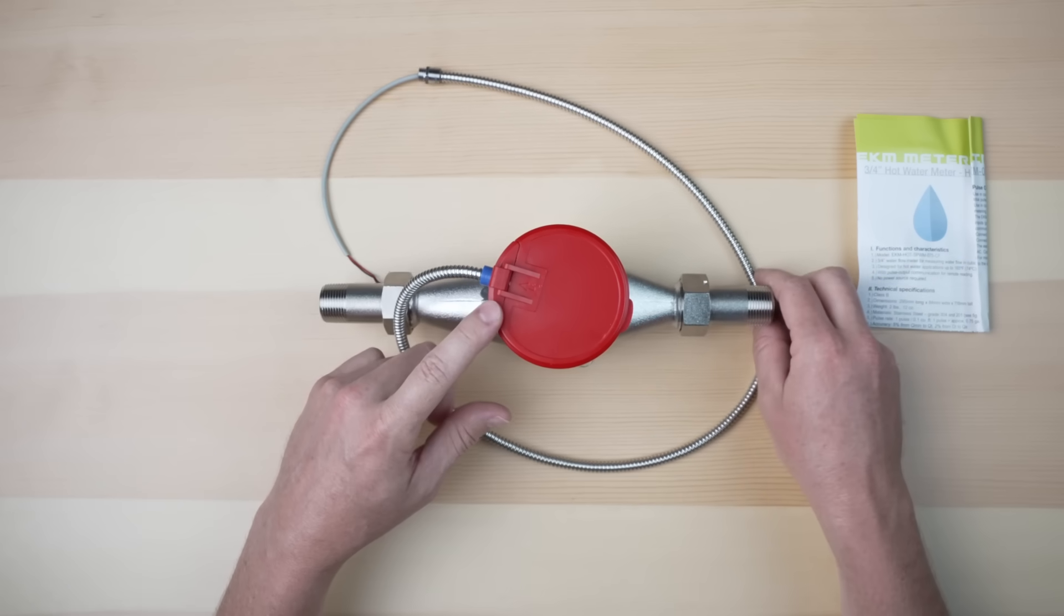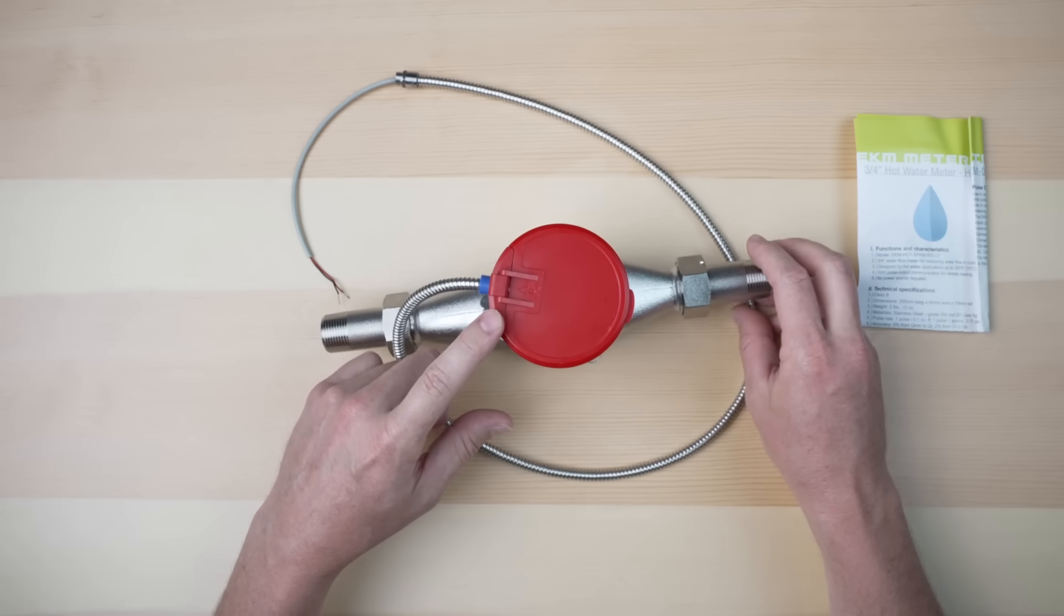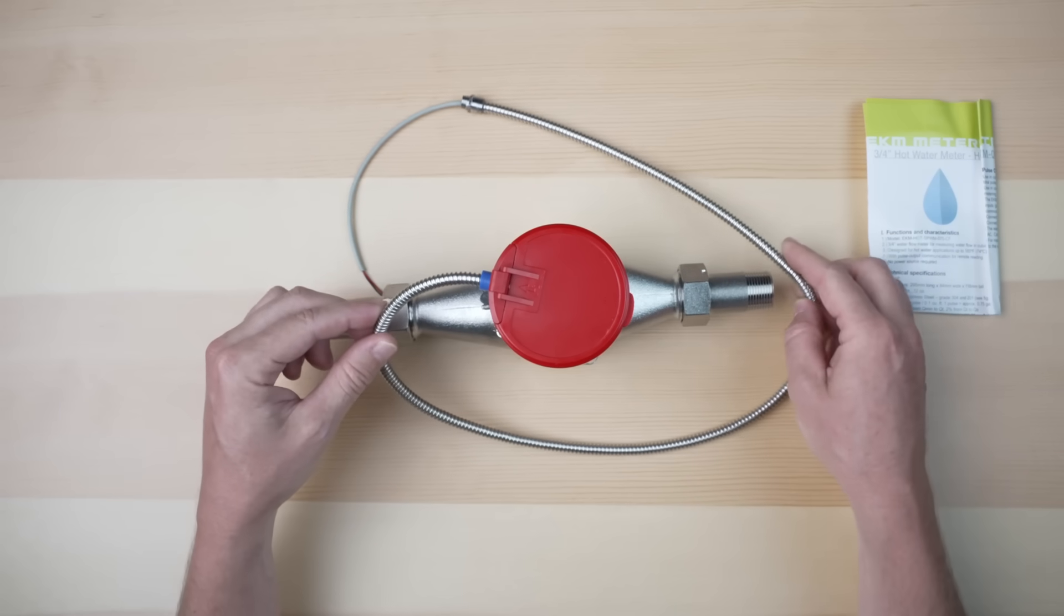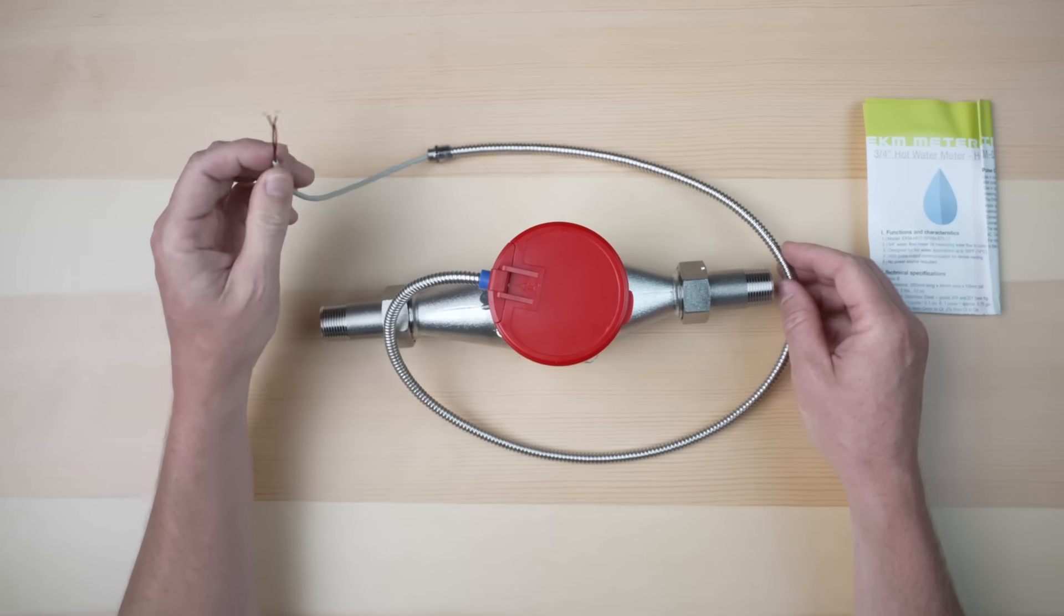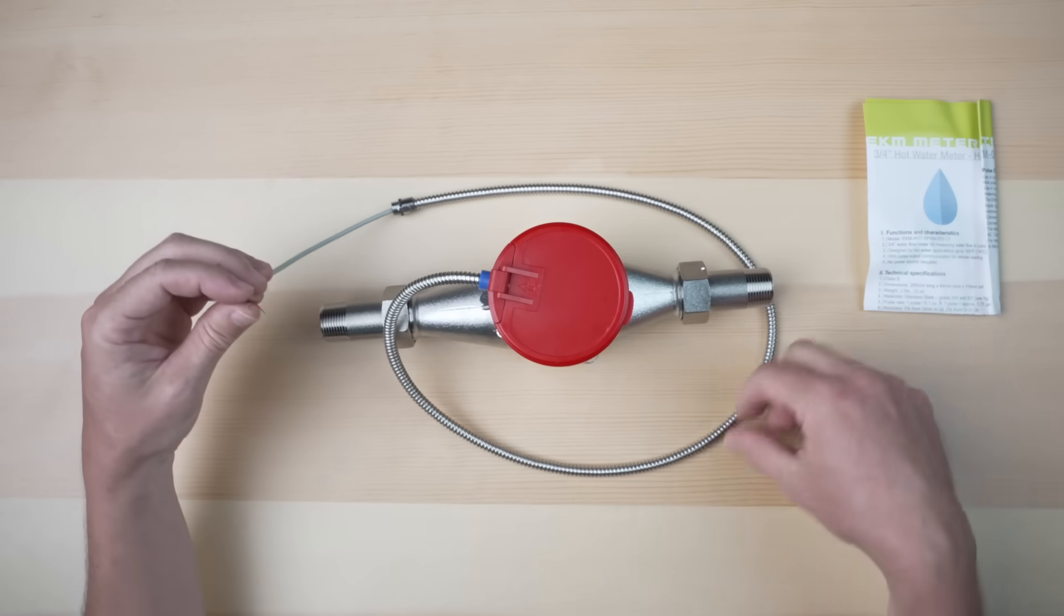The pulse output is rated at a maximum of 20 milliamps at 24 volts DC. The metal sheath is 30 inches long and the wires are 38 inches long overall, but they can be extended to thousands of feet if needed.